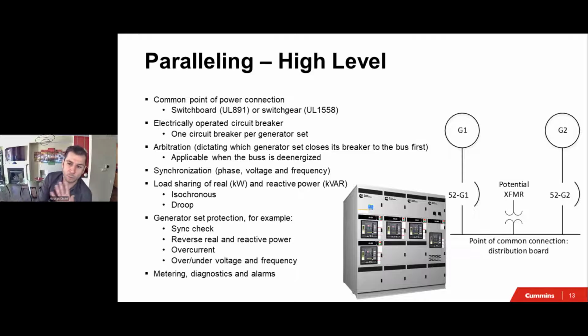So when it comes to paralleling, we're going to go high level, then dive down a little bit. Since you're going to earn a PDH from this course, we're going to have to talk about some technical information. It's going to get a little dicey, but that's okay because you can handle it. So for paralleling generators, from a very high level, we need a point of common connection, a point of power connection. These are where the cables are connected. This is the point where the generators are providing power to the loads, and this is what they reference when they connect together, reference that voltage, and do the sensing.